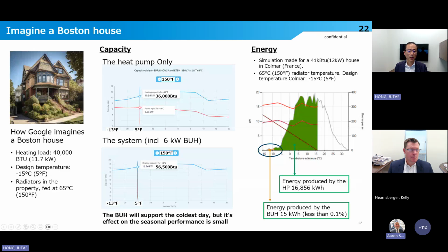Now, let's imagine a house in Boston. Let's say their heating load is 40,000 BTU with 150 radiator and 5 design temperature. At a 5 ambient temperature with 150 living water temperature, Daikin Altherma provides 36,000 BTU with heat pump operation only, which is close to the heating load. When you consider the 6 kilowatt booster heater inside the indoor unit, the total capacity will be 56.5 thousand BTU.